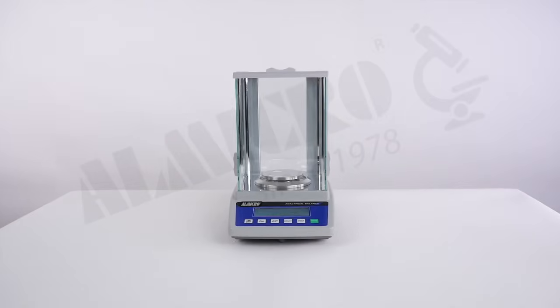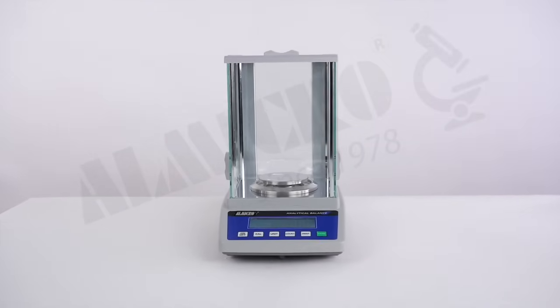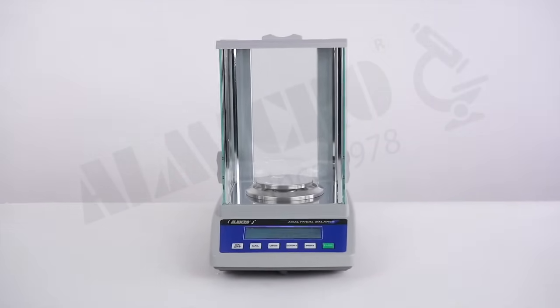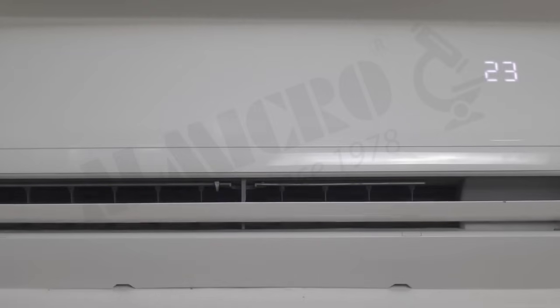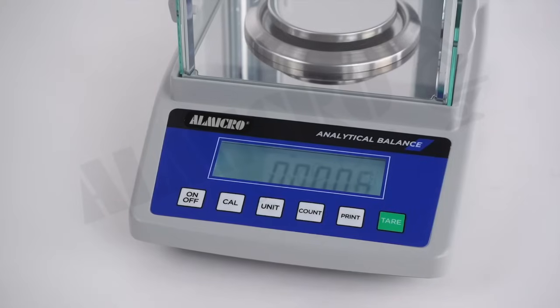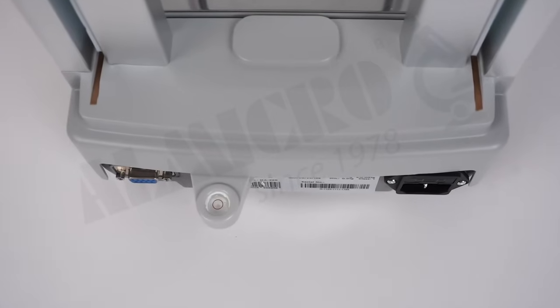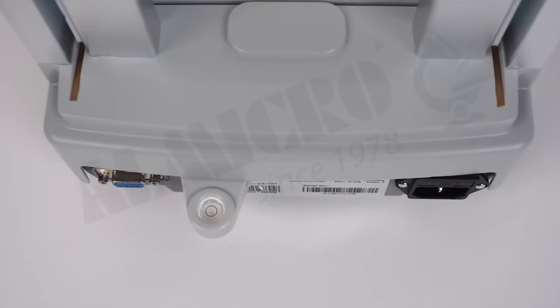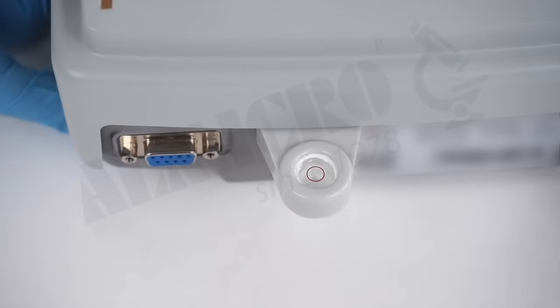First consideration is selecting the workspace. Your analytical balance needs to be placed on a steady, stable surface. The balance should not be used near doorways or air vents because it is sensitive enough to be affected by air. Check to see if the balance is level. Adjust the feet until the air bubble is inside the black ring.